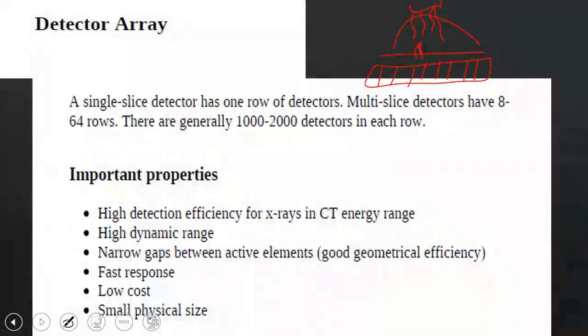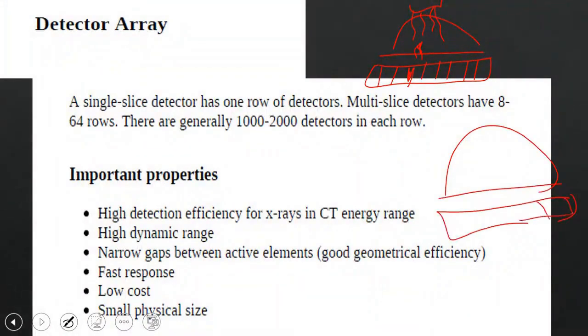A high fraction or percentage of the transmitted X-ray beam that comes back from the patient is significantly important, as it relates to geometric efficiency. This geometric efficiency is very crucial and can be significantly affected by the dimensions of the detector, the position of the detector, and the gaps present. For example, if I have the patient here and the detector here, and I divide the detector into elements, if there is a gap between this detector element and the adjacent one, then there is a part here that significantly reduces the geometric efficiency, which in turn significantly decreases the percentage.